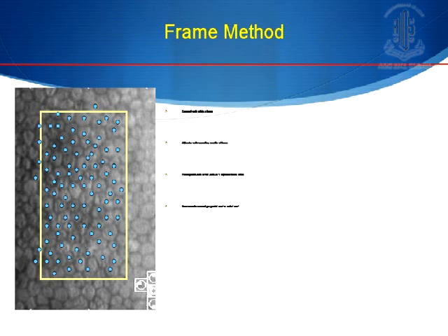There is a frame method in which, in the software, you just highlight a part of the frame and that automatically picks up the center of the cells and counts them and then gives the various parameters. You can use a variable frame analysis as well. There is a centration method in which you have to pick out manually the center of the cells, in either a circular fashion but practically it's easier to do it in the form of a rectangle, and then the software analyzes the size, shape and the hexagonality.